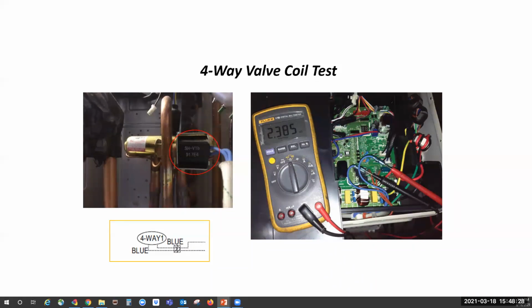Now you want to turn off your power, and you're going to use your digital test meter to check the resistances. And the resistances should be between 1.8 and 2.5 kilo ohms. So just so you guys caught that, that is 1.8 and 2.5. And of course, you want to make certain everything is open to ground. If it's not open to ground, you're going to replace your coil.